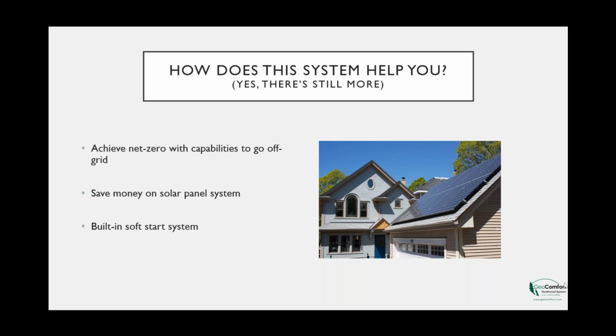And again, with net zero, we cannot achieve net zero with a fossil fuel system. Once you burn that fossil fuel, it's gone, it's done. So the only way to achieve net zero is through an electric-driven device, and the best there is a heat pump. And of course, the best heat pump is a geothermal heat pump versus an air source because of the temperatures and the free energy we're pulling from the earth. And now with this new all-in-one variable speed, we can do the hot water, the heating. We've got the built-in soft start. So it's a tremendous product to incorporate that net zero if you really want to go that direction.